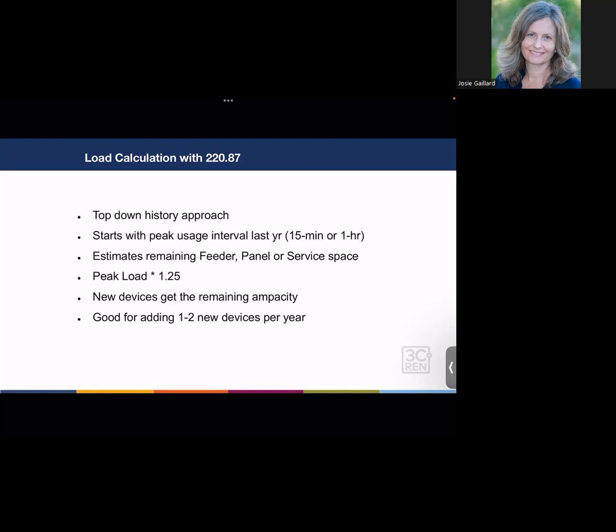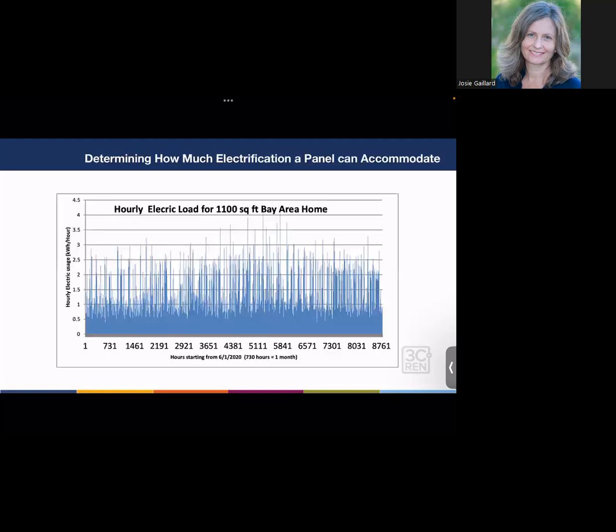We use this approach when we're just trying to add 1 or 2 new devices and we've got a historical load. We've got all that data for the home, meaning they've been in the home for a year, they have all that data available, and it shows that they've got plenty of space on their panel. This is a really good approach. However, we do have that issue of we have to apply 100% of the load. So if you're adding a 40 amp range, for example, you have to apply all 40 amps in this calculation.